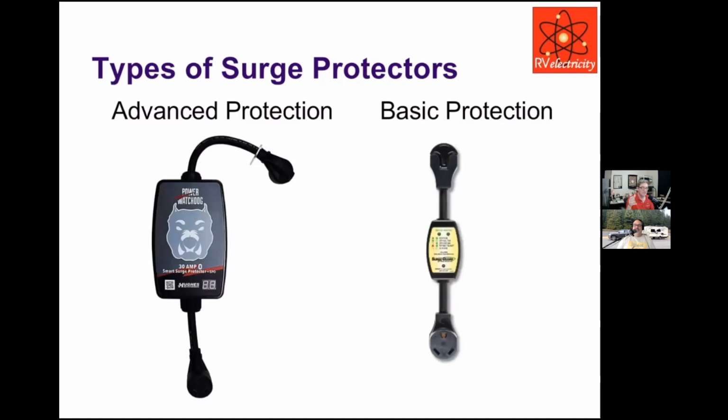Now, interestingly, I've had a number of campgrounds complain. None of these guys actually say anything's wrong. It's only those guys with those surge protectors that complain about the power. Nobody else cares. Everybody else accepts it. And let me tell you the most dangerous thing: an old campground with a new outlet, a new pedestal, because somebody put it in who probably is not electrically trained. I got bit in an old church with a new receptacle on the wall.